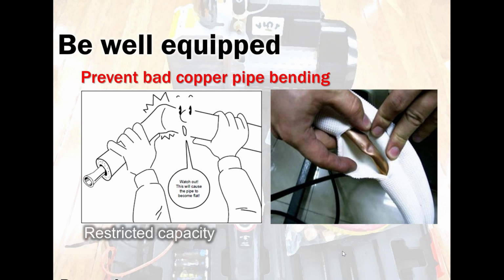In this case, the guy blamed the manufacturer of the pipe. And I said, okay, yeah, it could be right. But why take chances? Use tools. Do a perfect bend. If you don't have a bender, go and get an elbow, a copper elbow, and if you need to braze, obviously when you're brazing, you need to use nitrogen.